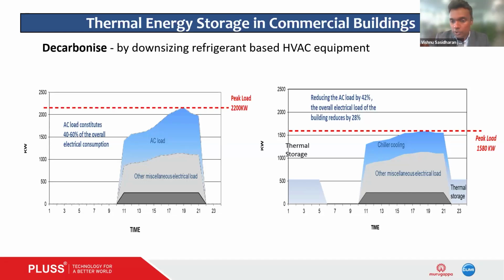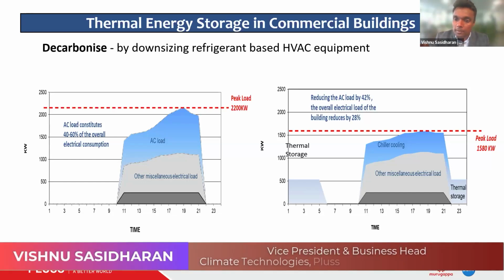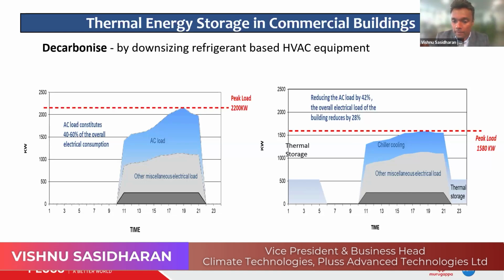It is integrated with your chiller systems, so the strategy could be a chiller-first strategy, where the chiller continuously caters to demand until a base load is reached, after which thermal energy storage comes in. This also helps chiller units work at maximum efficiency, mitigating part-load inefficiencies.